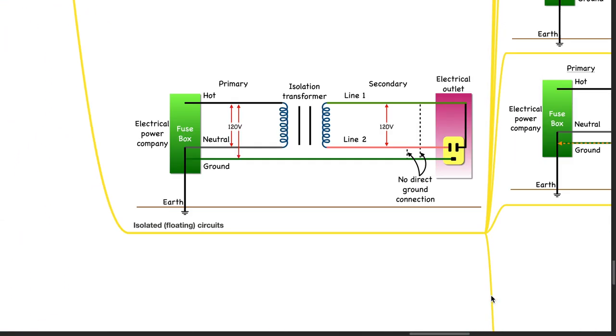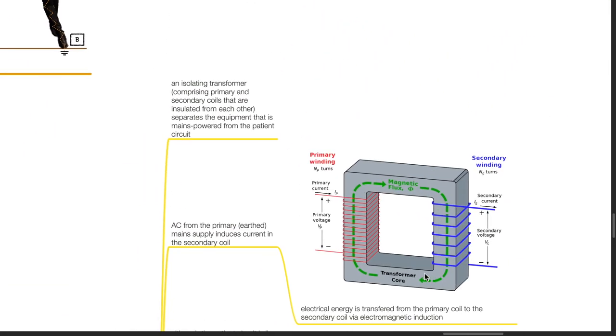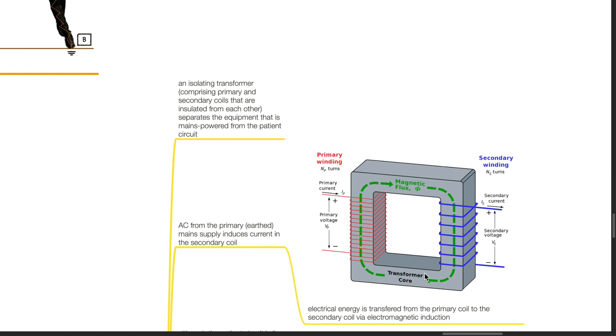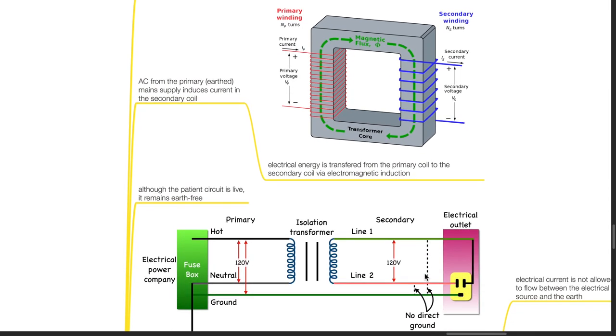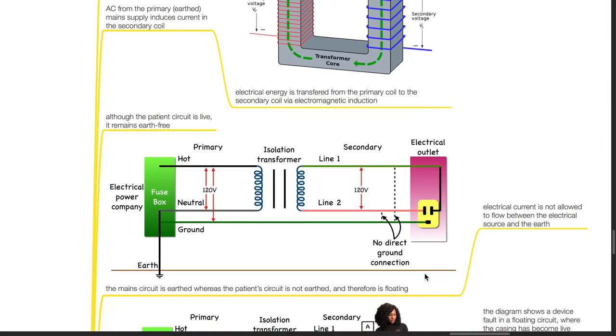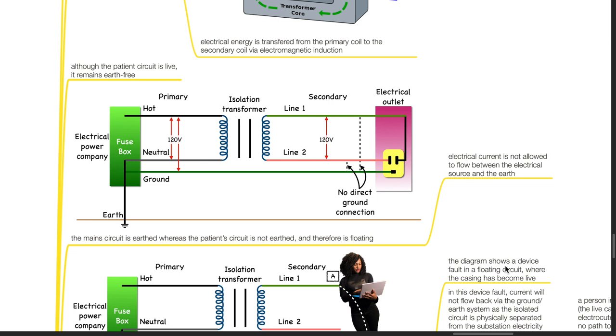Use of isolated or floating circuits. An isolating transformer comprising primary and secondary coils that are insulated from each other separates the equipment that is mains powered from the patient circuit. AC from the primary earth mains supply induces current in the secondary coil. Electrical energy is transferred via electromagnetic induction. Although the patient circuit is live, it remains earth-free. The main circuit is earthed, whereas the patient's circuit is not earthed and therefore is floating. Electrical current is not allowed to flow between the electrical source and the earth.